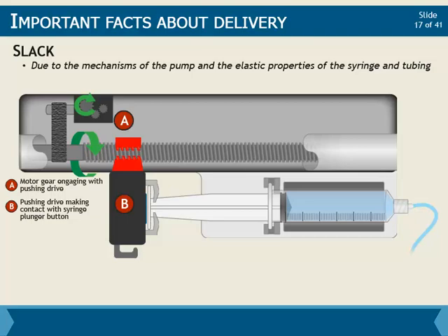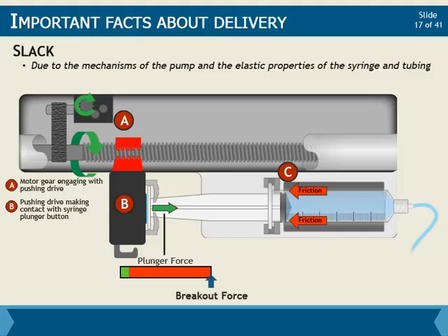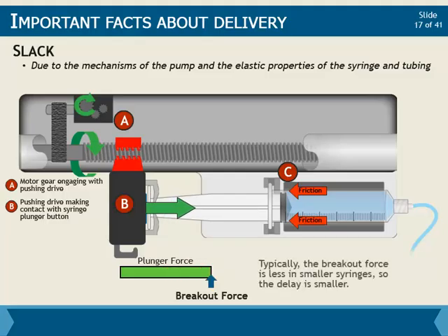Next, before the syringe plunger actually starts to move, the rubber head of the plunger must overcome the friction of the syringe barrel that is opposing its movement. The force required to do this is called the breakout force, and it takes time for the moving pushing drive to build to this force before the plunger actually starts to move. Typically, the breakout force is less in smaller syringes, so the delay is smaller.